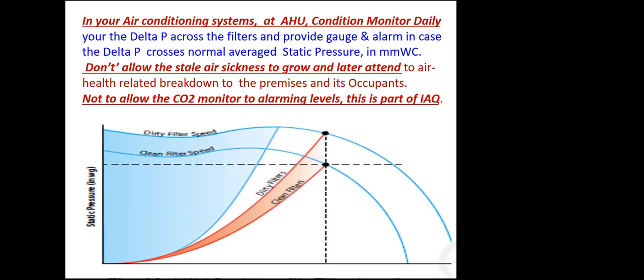is also having a problem with the delta P across the filters. The more choked the filters, automatically the blower efficiency drops. You can see the dirty filter and the clean filter. So much static pressure is increasing. The static pressure has to be kept optimum. It is to be monitored. So we know condition monitored filters, what the filter can operate with at minimum, what it can operate with at maximum, and what is the operating pressure drop across the filter. These are all the points. The HVAC auxiliaries have to be given to the user as such, the consumer as such. Next, please.